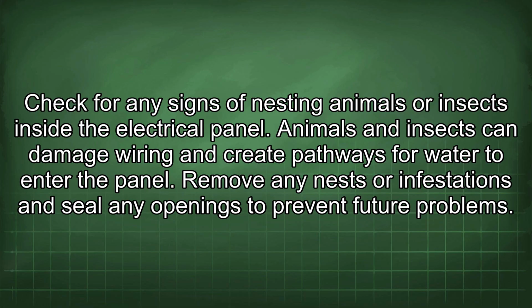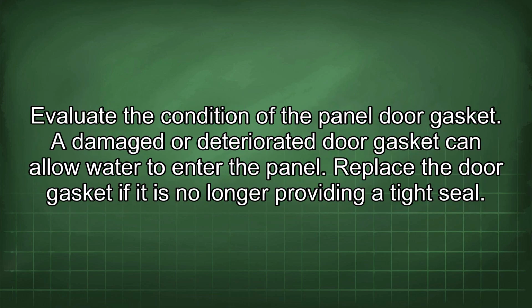Check for any signs of nesting animals or insects inside the electrical panel. Animals and insects can damage wiring and create pathways for water to enter the panel. Remove any nests or infestations and seal any openings to prevent future problems. Evaluate the condition of the panel door gasket. A damaged or deteriorated door gasket can allow water to enter the panel. Replace the door gasket if it is no longer providing a tight seal.